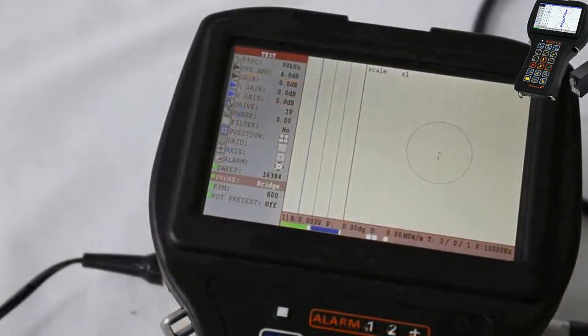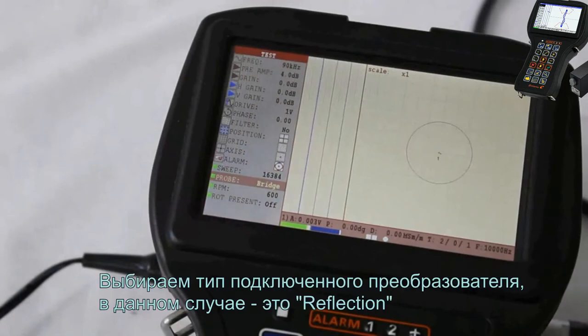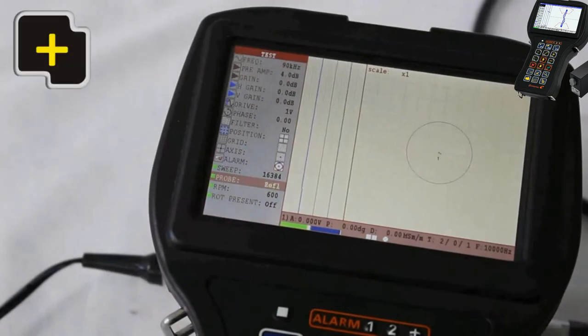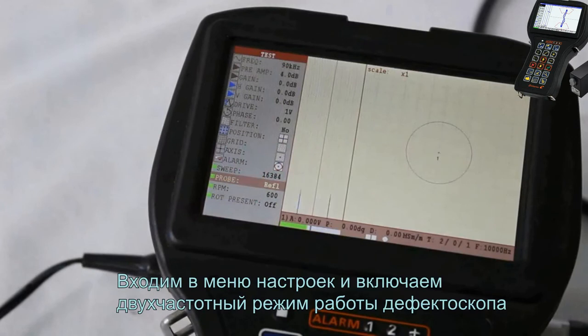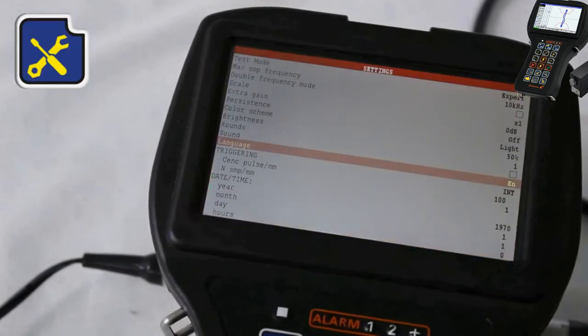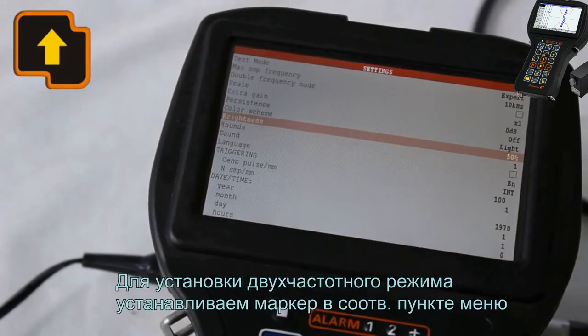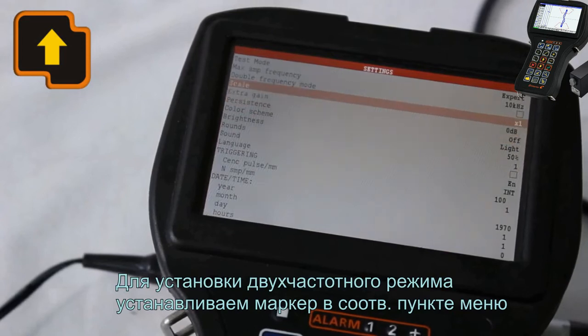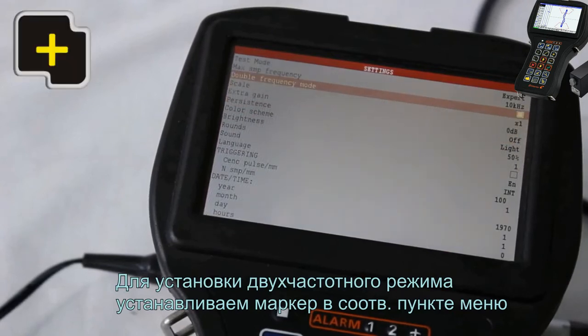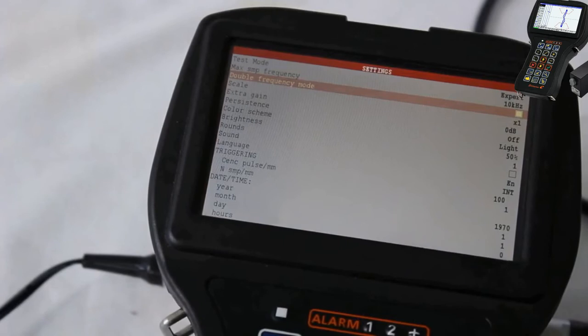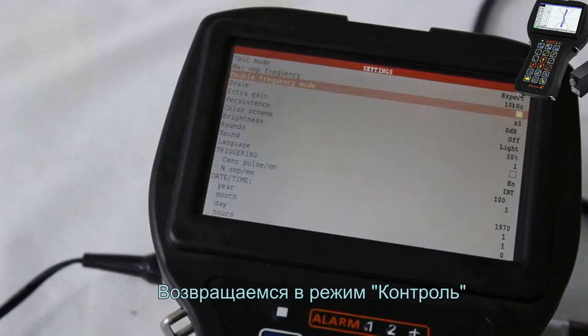Due to the capability to create the mix of two frequencies, it is possible to suppress the interfering factors and decrease their influence on a test result. Select the type of a connected probe. In this case, it will be reflection type probe. Enter the settings menu and switch on the double frequency mode of flaw detector operation. To set up the double frequency mode, click the marker in a relative menu item. Return to the test mode.